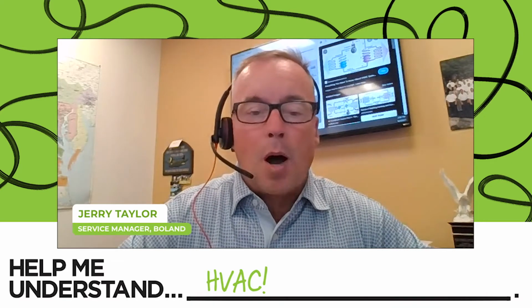But so you used a couple of terms there that I think it would be helpful if we defined and talked a little bit more about the various components that make up an HVAC system. So what are some of the primary components that make up an AC system that people should at least be aware of? Certainly. So every air conditioning system is going to have four basic components, regardless of the capacity, the size, the type of refrigerant you're using. But each system is going to consist of at least one compressor, which is basically a pump. It's there to create a differential in pressure, pull refrigerant in at a low temperature, low pressure, squeeze it or compress it, and then put it out as a higher temperature, higher pressure gas.